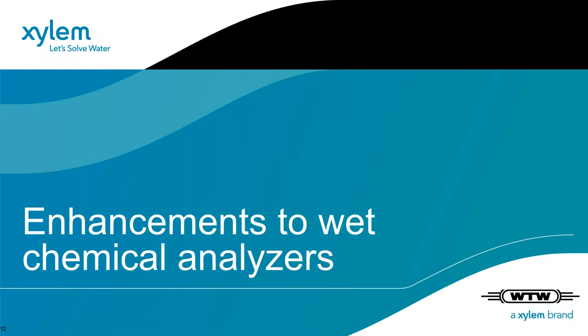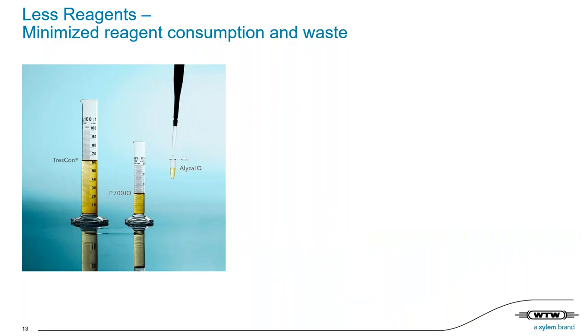We just now reviewed 2 of the most important features of the Alyza, the multiport valve and the chem bags, and already mentioned some of the benefits. Now I would like to give you some more insight into the enhancements and thus benefits of this new analyzer technology. As I keep mentioning, the reagent consumption of Alyza IQ is really extremely low. Here you see a comparison of all 3 WTW analyzer generations shown per day with a 10 minutes interval.